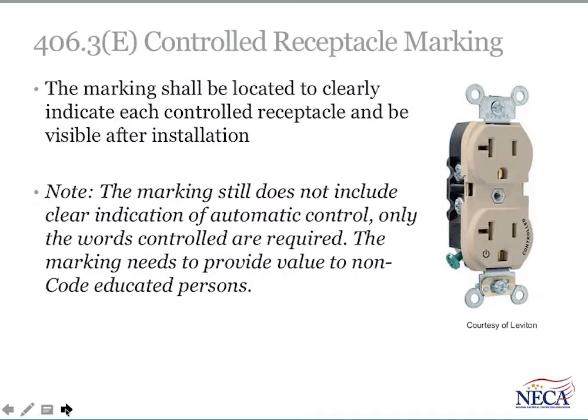In the previous edition of the NEC, we had the requirement for the universal power symbol on the receptacle, but to the normal user of the receptacle in the field who may not have knowledge of the NEC, it was unsure to many of them what that meant. The change requires the word "controlled" be included in addition to the symbol on the face of the receptacle. That gives the occupant a sense that the device is controlled, and in this case it's automatically controlled through energy management.